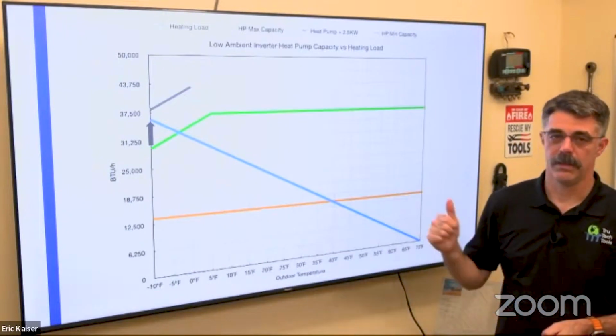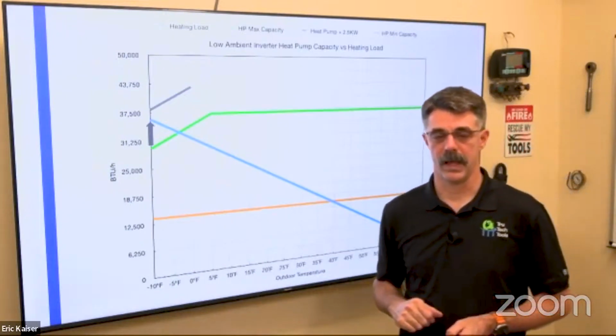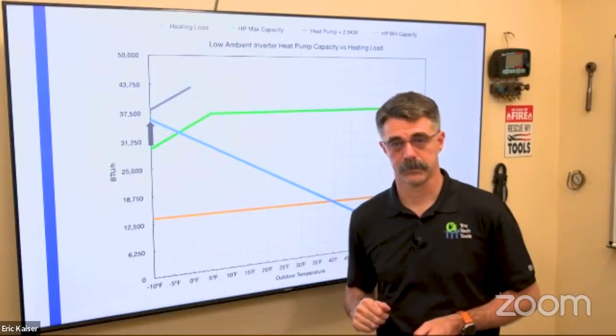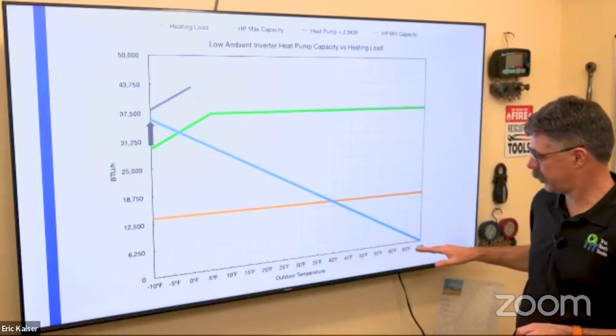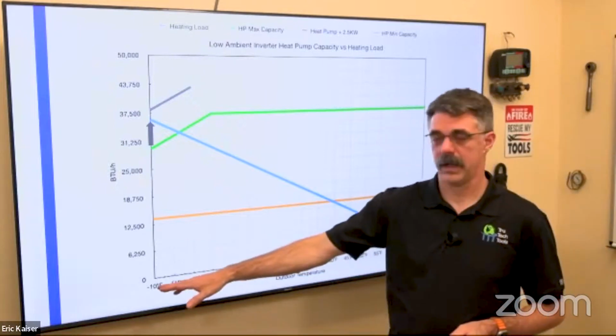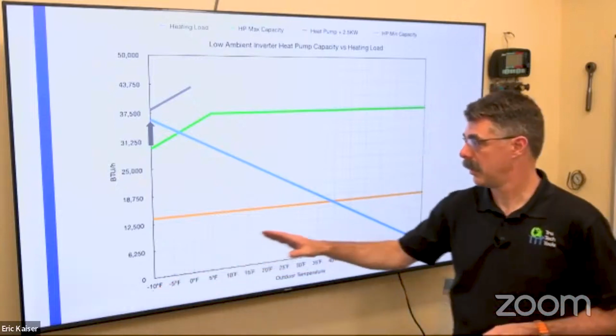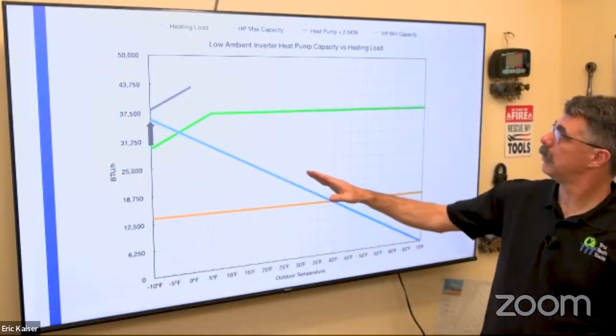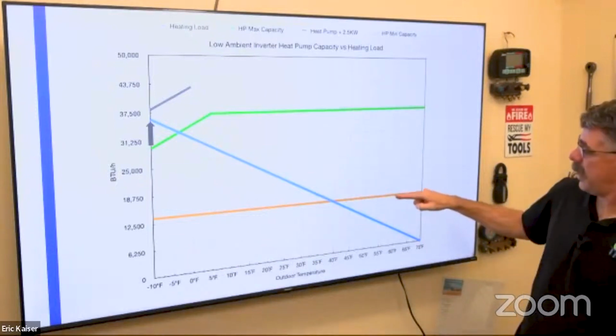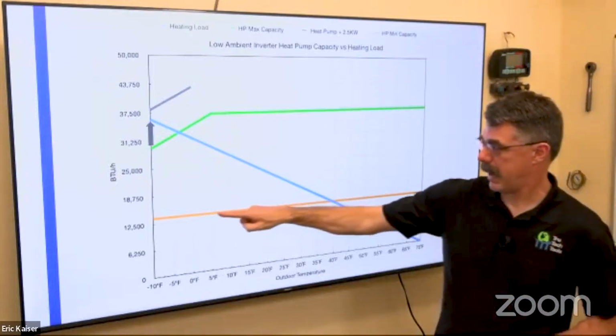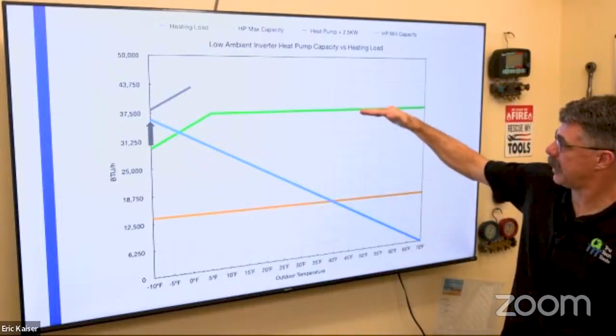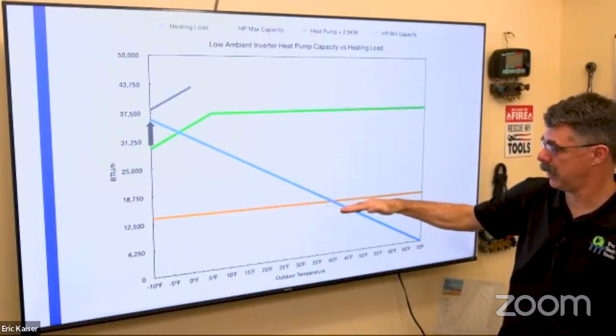All right. This is an example of a cold climate heat pump. So our scales changed a little bit down here. Now we're going all the way down to -10. Okay. Same slope on the house. All right. And this is the heat pump minimum capacity line down here. So that capacity can vary anywhere in between here.